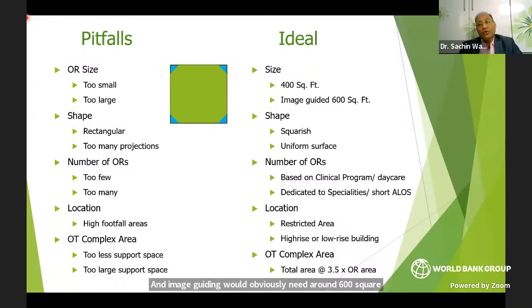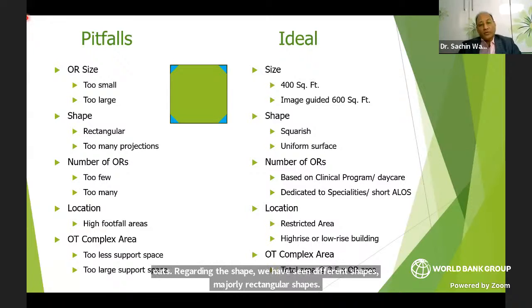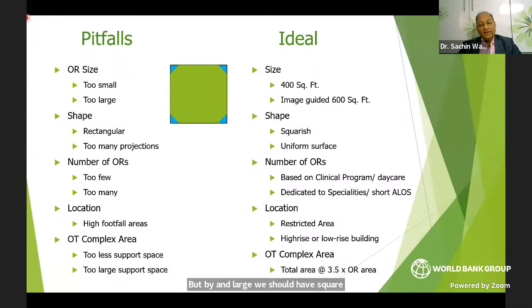Too large OTs are also not good because they increase the surface area, and that increase will also increase the contact for opportunistic infection. So unnecessarily, we should not have too large OTs. Regarding the shape, we have seen different shapes, majorly rectangular. But by and large, we should have squarish OTs, so that the length is equal to breadth. The reason for that is the airflow, which I'll discuss in the next slide. We should also avoid too many projections, like columns, ducts, shafts, and adjoining walls. We need to maintain the wall surfaces as uniform as possible.